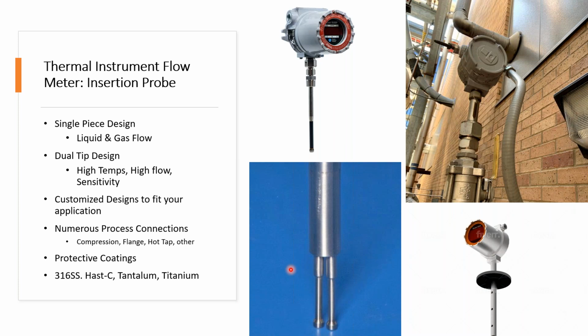We also can customize a lot of these units. So we can make them different lengths. We can make them different ODs in order to hold up to different conditions. So if you need a flange connection, as shown over here, we can do that. If you've got a large line size and maybe you've got some turbulent flow conditions because you've got some bends or different things in your piping creating some turbulence in there, we can put multiple sensing points as shown on this unit right here, where we can take flow at different points going across the line. So again, the insertion probe is very customizable, material-wise, process connection-wise, coatings, you name it, we've kind of done it, and we can build these to suit a wide variety of flow applications.